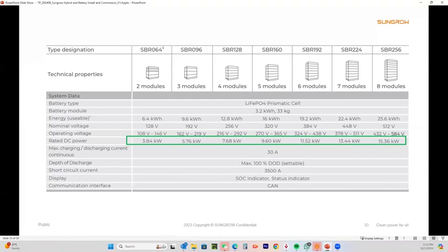If the loads try to consume more than that, the system will trip, okay? So if somebody does want to get 10 kilowatts of power available on the backup, you're going to have to go up to this size here, 6 modules, okay? Bear in mind, 2 of these in parallel, this is all going to be the same except the capacity will double. The voltage, the current, the power is going to be the same. So they need to go to 6 modules.